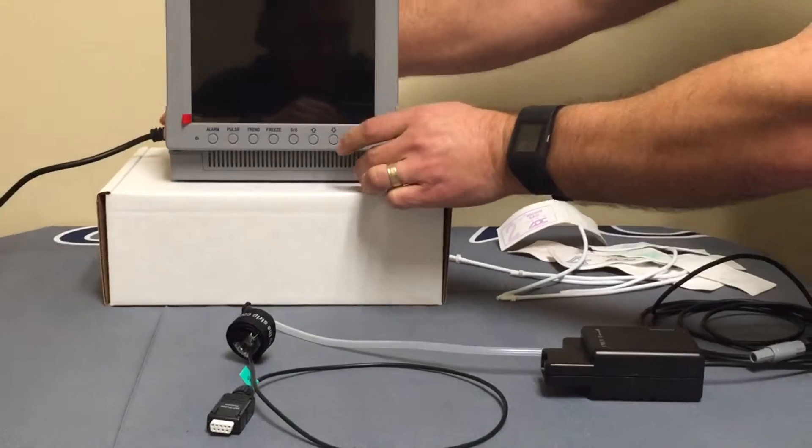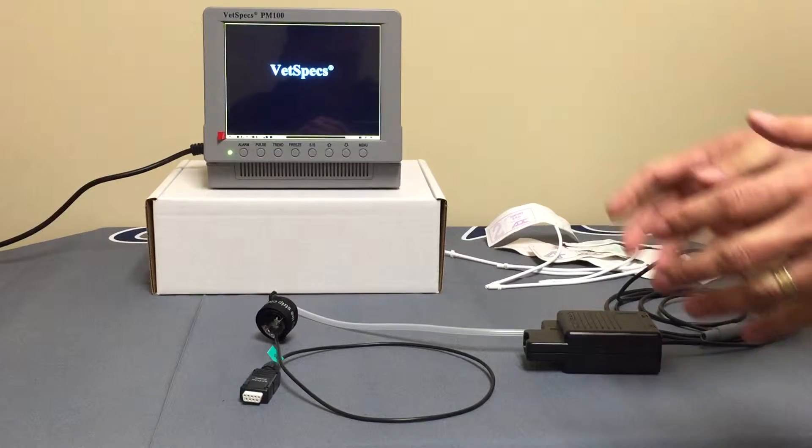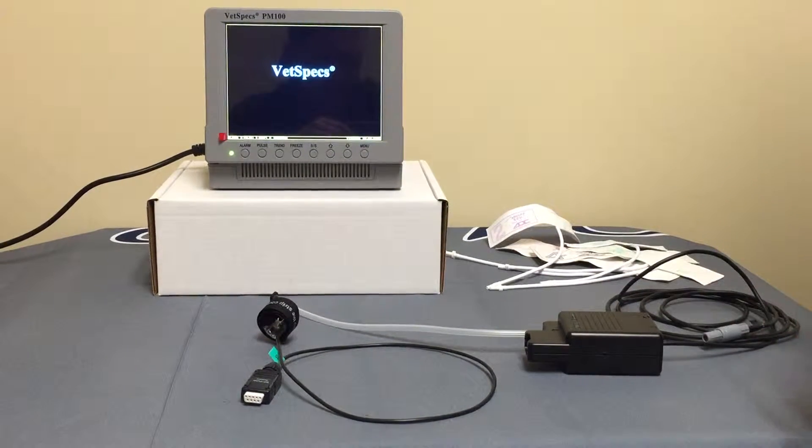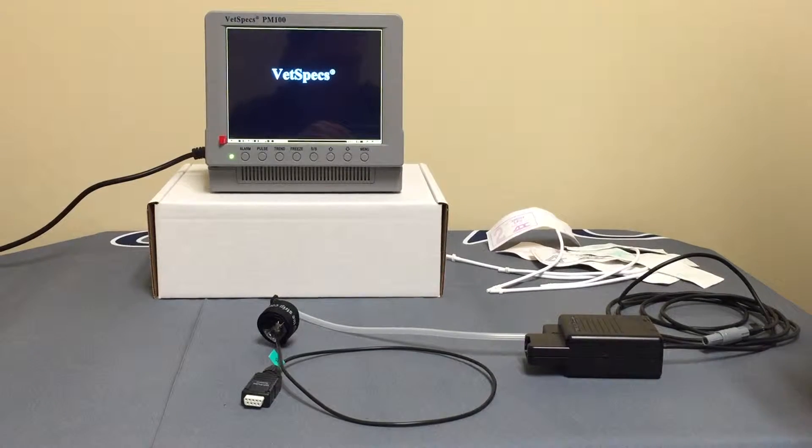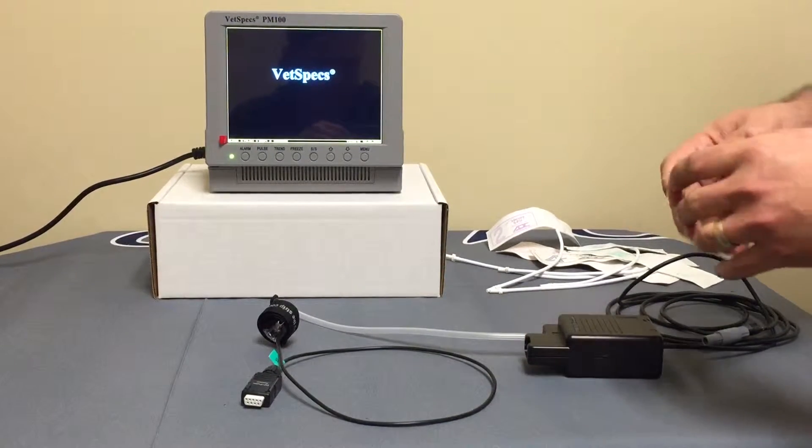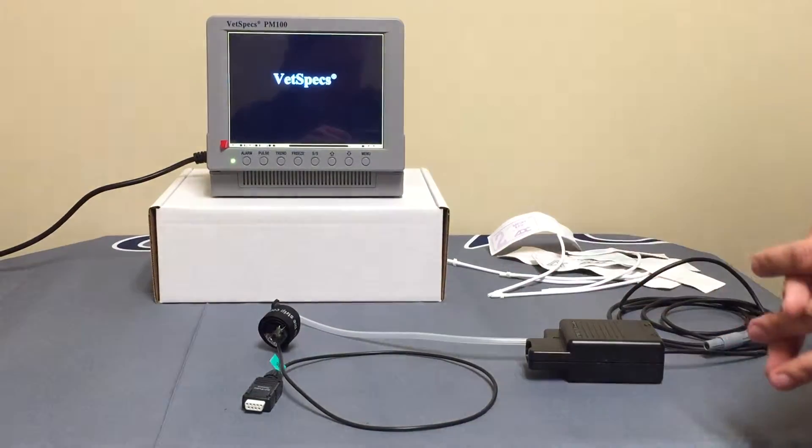This ought to work. I didn't mention it earlier, but one of the other features of the VetSpecs PM100 monitor is that the different modules that are available—I'd shown earlier the multi-parameter main module and the blood pressure module, there are actually several other modules available—but the two modules that you'll find prevalently with the system as far as surgical monitoring are the blood pressure and main module.